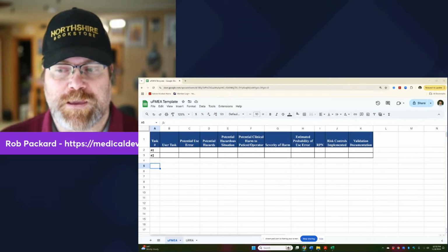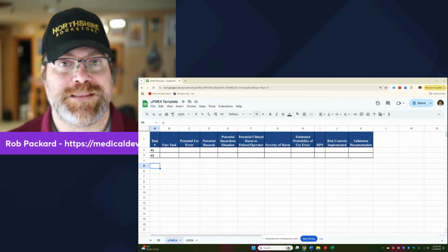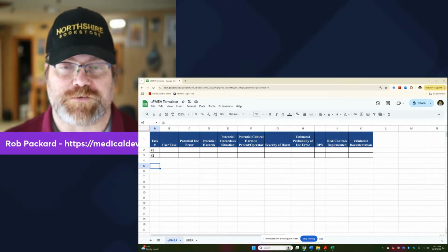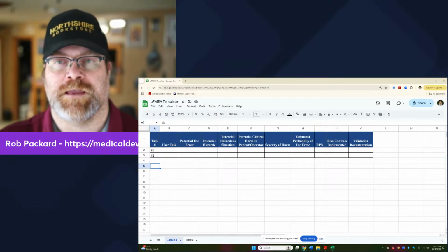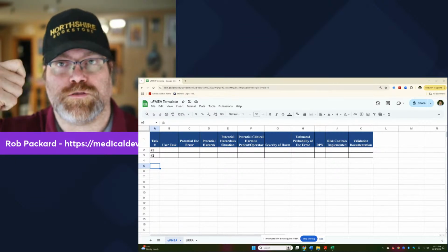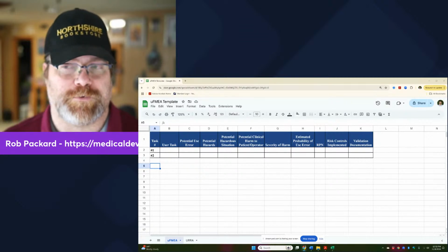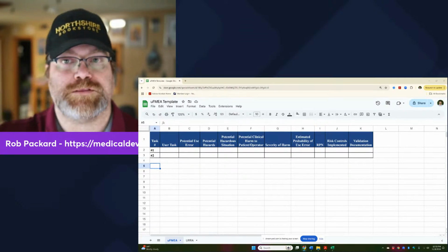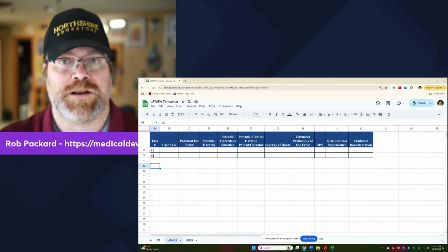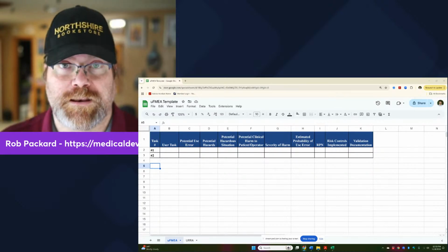Column B would be each of the tasks that's performed. Column C would be the potential error that a user could make. So you try to brainstorm, how could this user make a mistake? They hold it so it touches the temple instead of holding it away from the temple by a certain number of centimeters or millimeters. They hold down the button, but not for long enough. They hold it down for too long. They don't hold down the button at all.